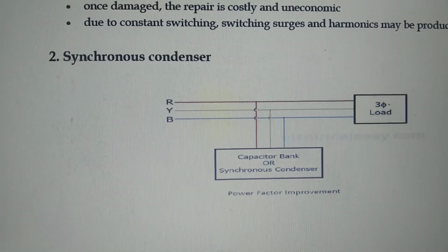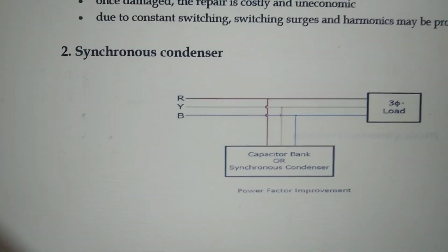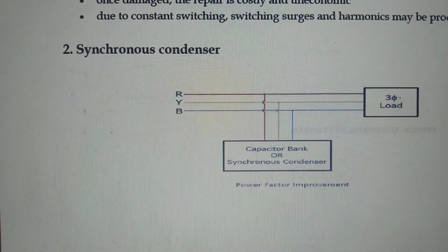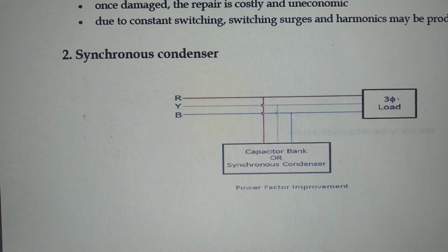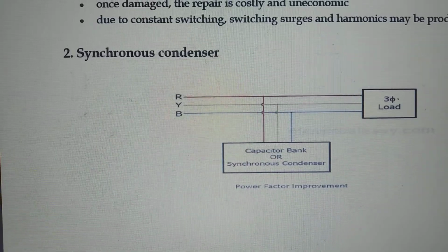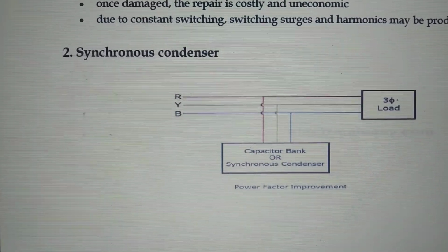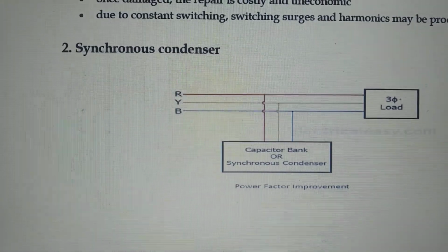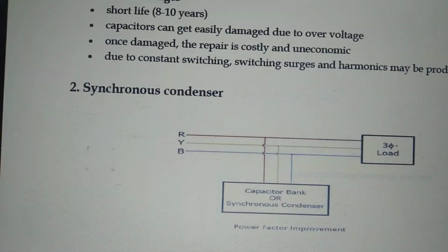The second one is the synchronous condenser. A synchronous condenser is a synchronous motor operating under no load condition, in an overexcited state. Overexcitation and no load condition, our synchronous motor is operating. This is called a synchronous condenser.